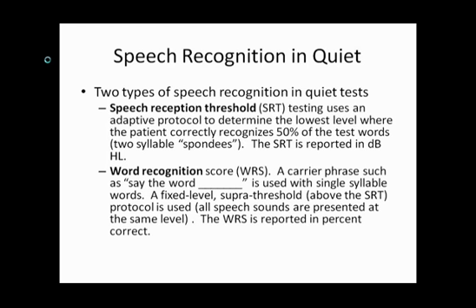There is also a fixed level protocol, meaning every single word or sentence is presented at exactly the same level. It is also called a supra-threshold protocol, meaning the speech is presented above the level of the thresholds — either above the pure tone average or above the speech reception threshold.